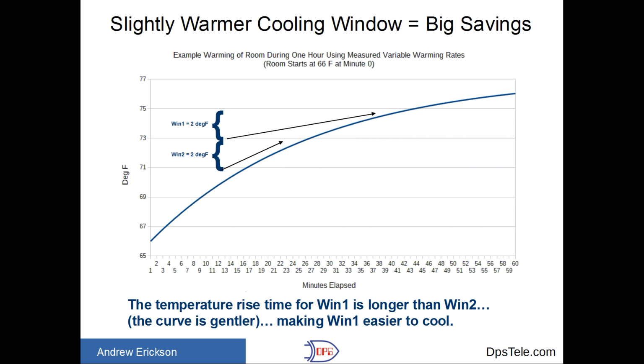to, instead of being in the 70s or low 70s, can we get to the high 70s or even into the 80s? The higher you can go, the more you're going to save when it's warm outside, because you're not fighting against those warm temperatures outside trying to keep your site as cool, and you're always going to save money. The same principle is at play in your house. I think everybody knows that if you don't demand it to be quite so cool or quite so warm in the winter, you can save a lot on your electricity bill.